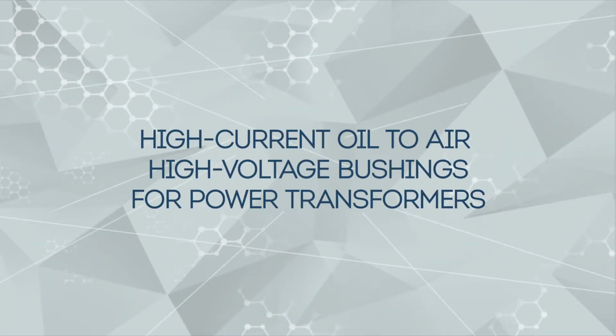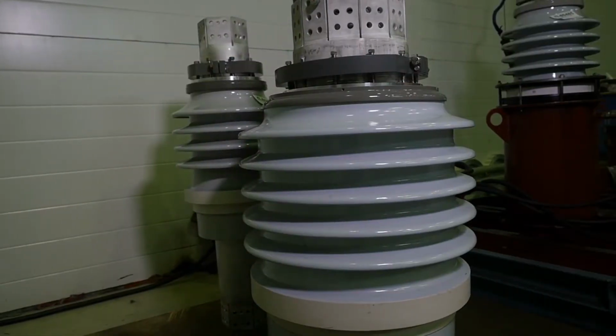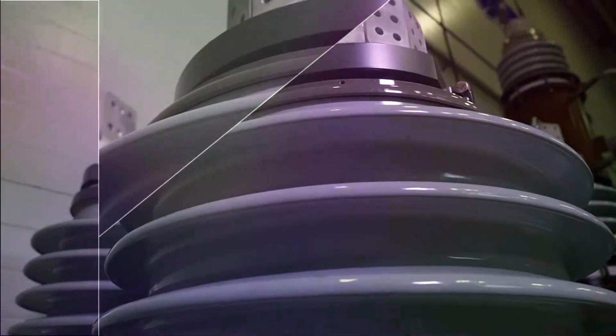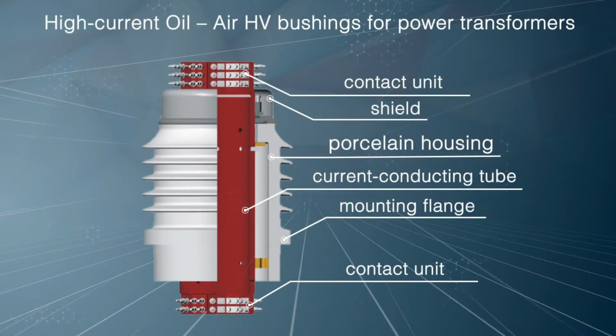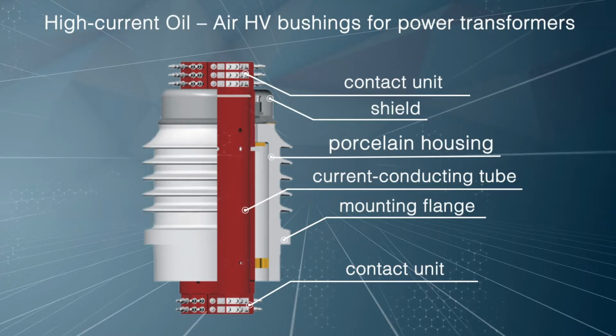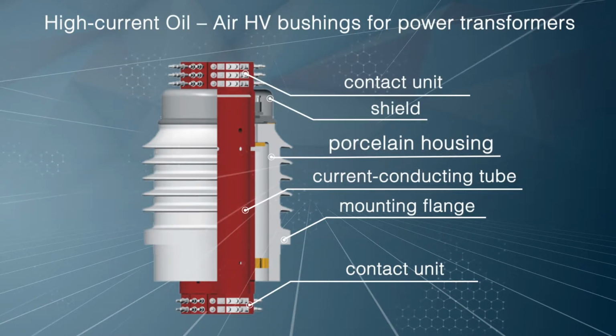High current oil-to-air high-voltage bushings for power transformers. These bushings are intended for connection and transmission of electric power produced by the generator unit of a power plant to the low-voltage winding of a power transformer. Design highlights of the detachable bushing: no internal insulation. Transformer oil fills the internal space of the bushing. Test tap is absent.